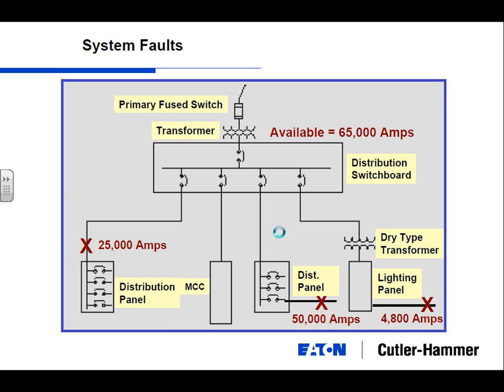So how much it costs to run a data center is how much energy they use, so that's a large chunk of it. When they look at designing a distribution system for a data center, they look very hard at removing as many of these dry type transformers as we can. You've been seeing a lot of changes in the voltages of data centers, where instead of stepping down to 120 or 240, they're doing things now at around 400 volts. A higher voltage means you may be able to get by with just one transformer that steps it down and use that across your facility.